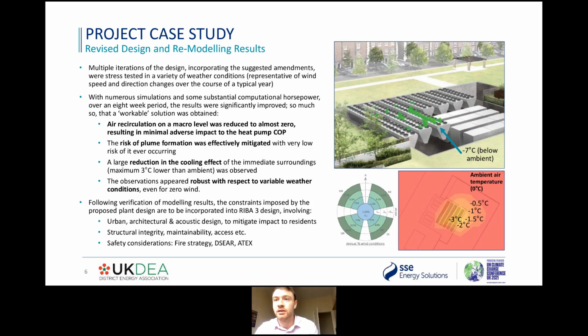You can see on the right the 7 degrees below ambient, which is your visible cold plume risk condition, is just that tiny bit of green extended from the air coolers. So basically, we've mitigated that issue. It's not going to be a concern.